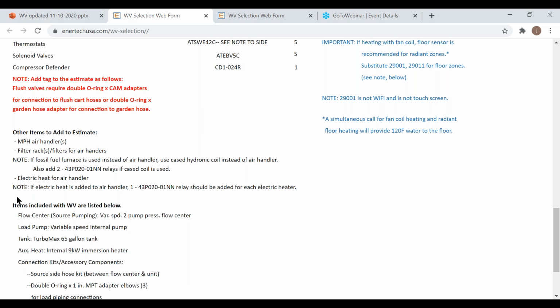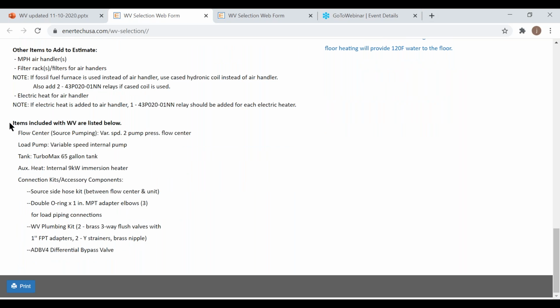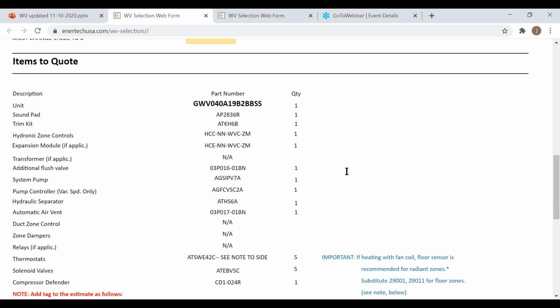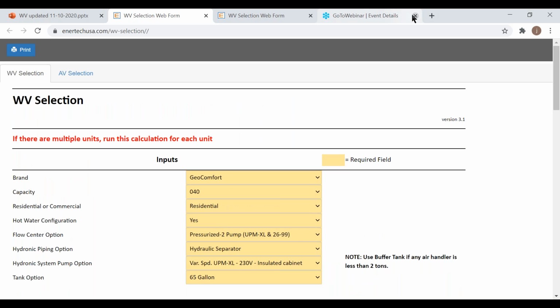So it'll list all the things that you're going to need. Other items that you might need to add to the estimate, you know, an air handler, filter rack, things like that. And then it'll also show items included with the WV listed. So it'll list your Y strainers, your FPT adapters, differential bypass valve, your tanks. So it'll actually spell out what's all going to be in the box for you. That's basically the WV selection chart.